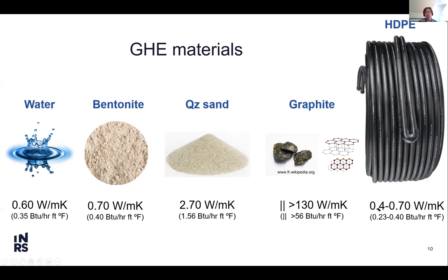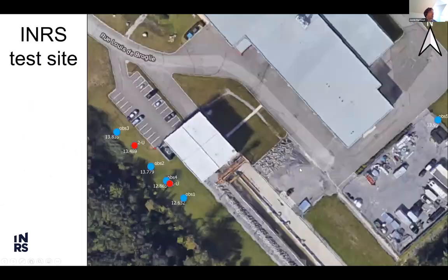This is a plastic pipe that is actually an insulator, so it's the weakest part of the well, we could say, in terms of heat transfer. The reason why people are using plastic pipe is because it's very robust, and the pipe can last a long time in the ground without being affected by corrosion, but it's not ideal in terms of heat transfer.